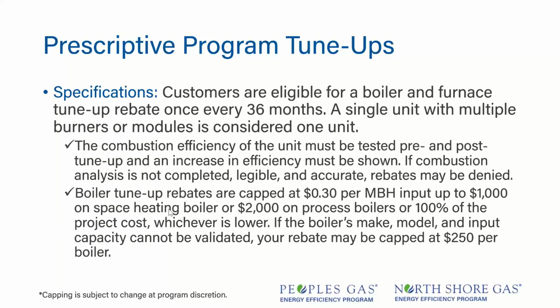Boiler furnace tune-ups. Customers are eligible for boiler and furnace tune-up rebates once every 36 months. A single unit with multiple burners or modules is considered one unit. The combustion efficiency of the unit must be tested pre and post tune-up, and an increase in efficiency must be shown. So we got to see some kind of increase, even if it's a 0.1, we got to see some kind of increase for the rebate for that boiler to be, the tune-up to be eligible for a rebate.